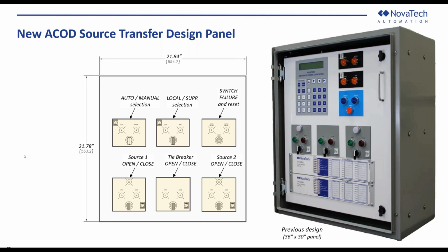For the consideration of a modern redesign, we've already seen that the OrionMX with the AC meter card and I/O cards can really simplify the devices needed in the system. That takes out the DDIOs because we don't need separate I/O devices anymore, and then also deleting the keypad that would be there and moving that ACOD configuration to an HMI screen means that we can pare down to just the necessary selector switches and indicator lights on the control panel.